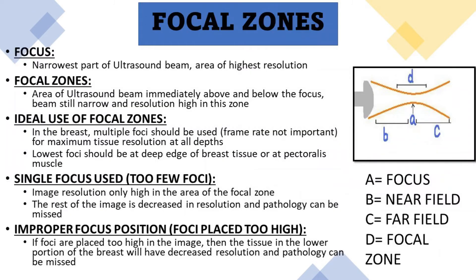Another essential ultrasound control to adjust is the focal zones. A focus is the narrowest part of the ultrasound beam and the area of highest resolution. Focal zones are the area of the ultrasound beam immediately above and below the focus, where the beam is still narrow and resolution is still high.